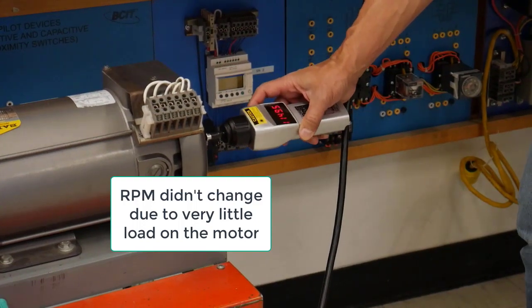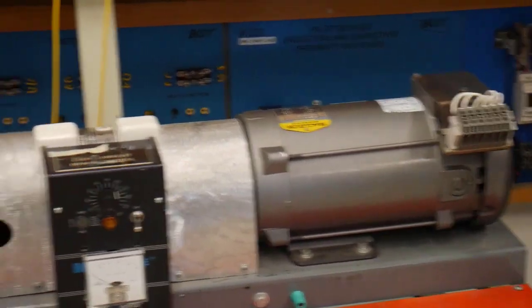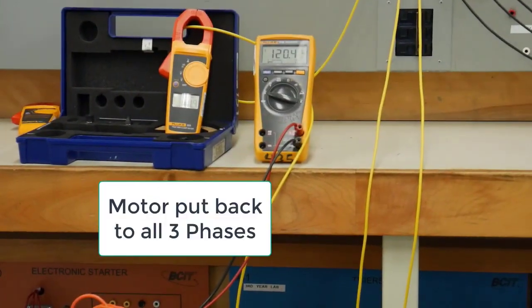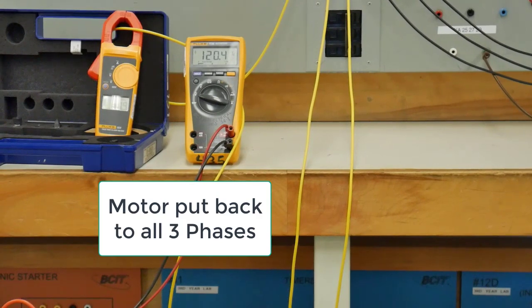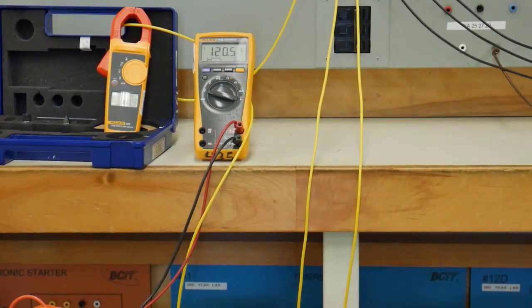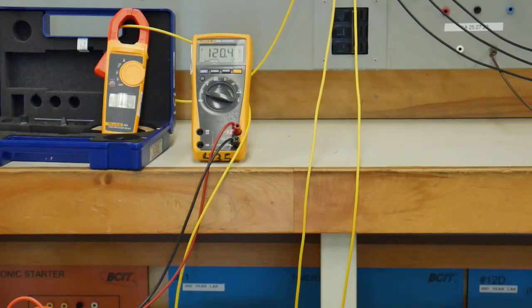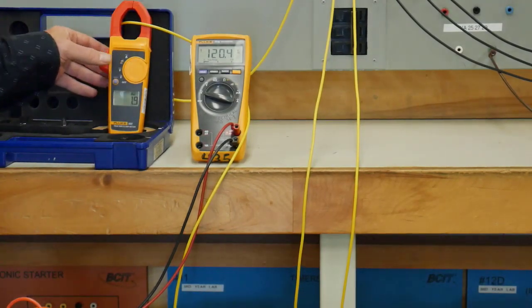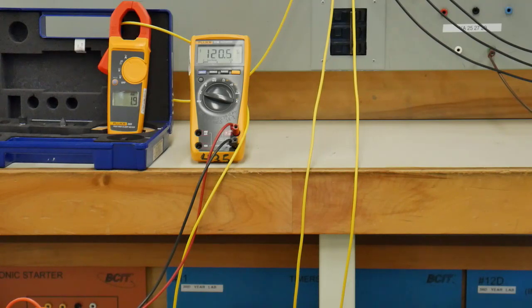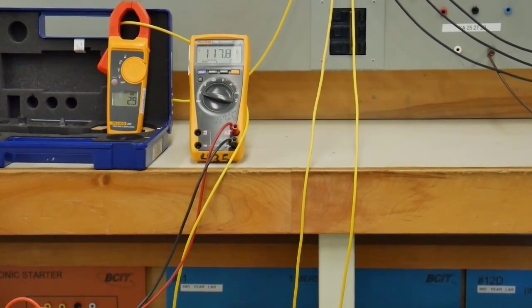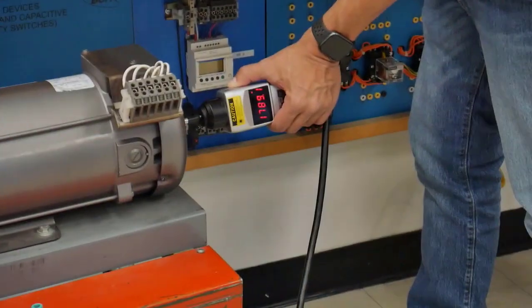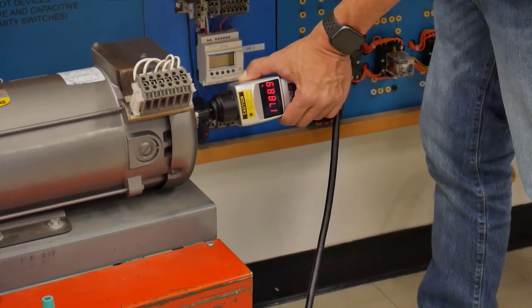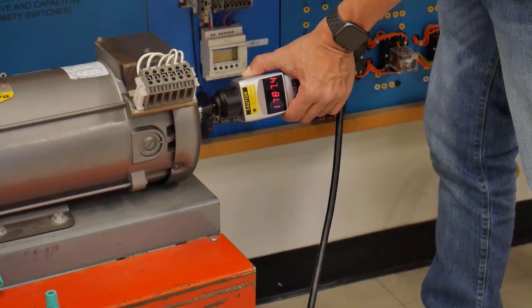We put it back to a three-phase condition, and again, not too much change. Now with our single-phase condition again, our current goes up to 2.9 amps. Our RPM is about 1789. Not a lot of drop in speed.